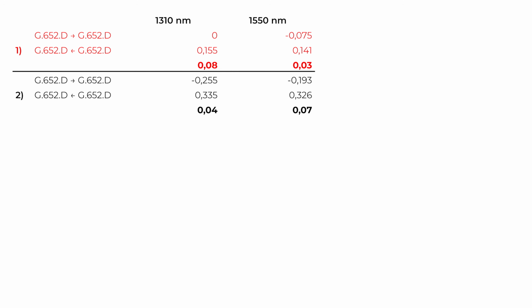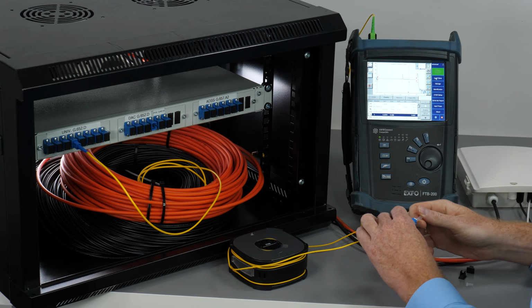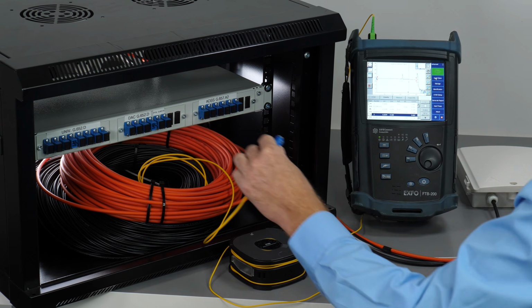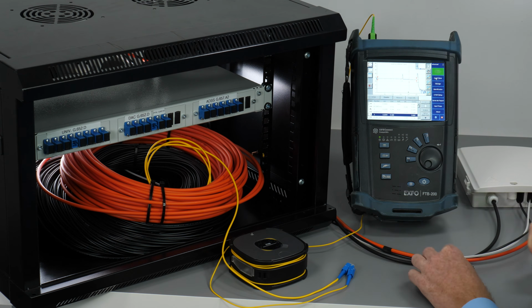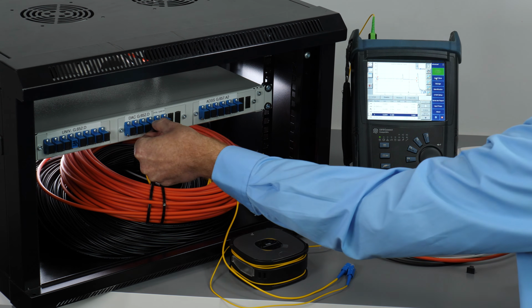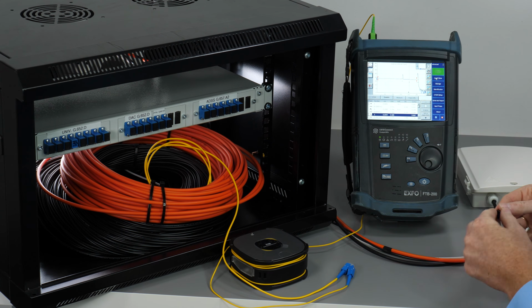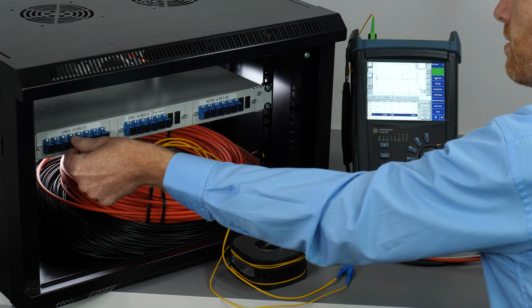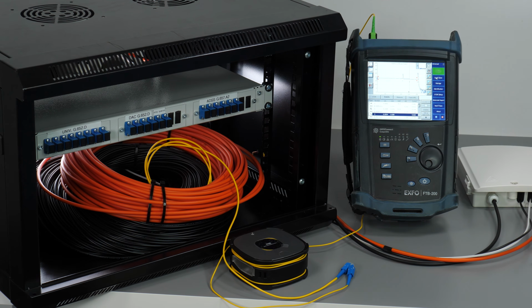Both splices should be considered as very good. Depending on the assessment criteria, which may be the operator's internal standards, structural cabling standards, or the recommendations of structural cabling system manufacturers, the maximum splice attenuation can range from 0.1 to even 0.3 dB. Most often it will be 0.1 or 0.15 dB.